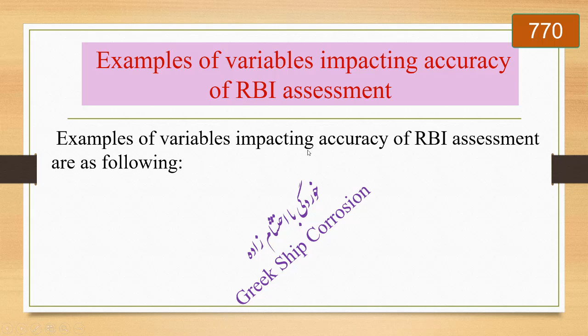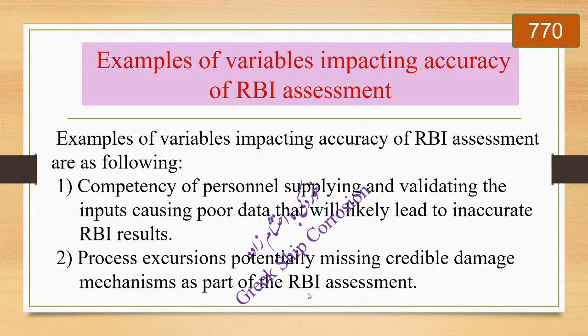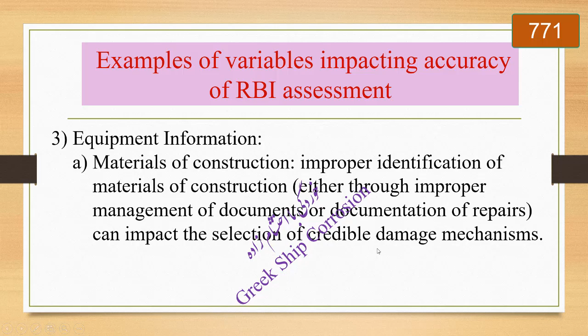Examples of variables impacting accuracy of RBI assessments are as follows. 1. Competency of personnel supplying and validating the inputs, causing poor data that will likely lead to inaccurate RBI results. 2. Process excursions potentially missing credible damage mechanisms as part of the RBI assessment. 3. Equipment information. A. Materials of construction. Improper identification of materials of construction, either through improper management of documents or documentation of repairs, can impact the selection of credible damage mechanisms.